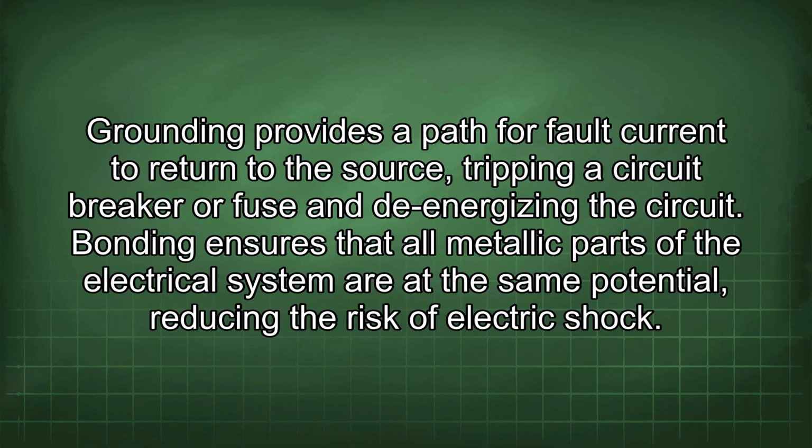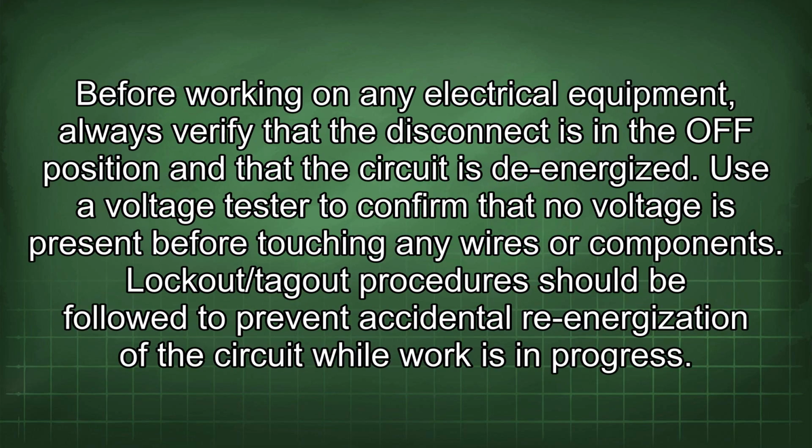of electric shock. Before working on any electrical equipment, always verify that the disconnect is in the OFF position and that the circuit is de-energized. Use a voltage tester to confirm that no voltage is present before touching any wires or components. Lockout/tagout procedures should be followed to prevent accidental re-energization of the circuit while work is in progress.